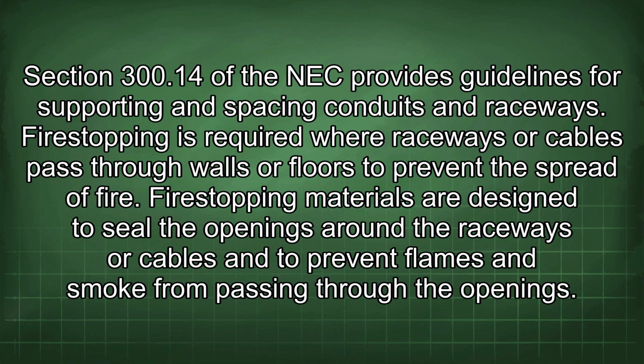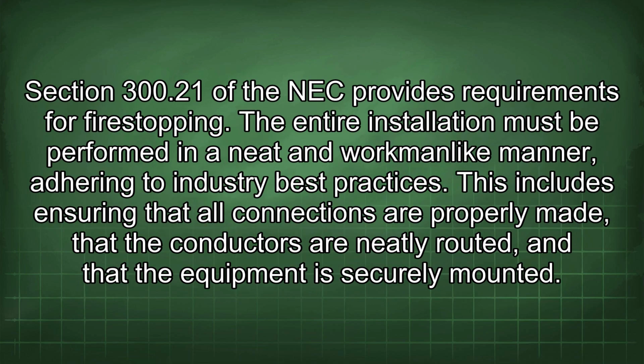Fire stopping is required where raceways or cables pass through walls or floors to prevent the spread of fire. Fire stopping materials are designed to seal the openings around the raceways or cables and to prevent flames and smoke from passing through the openings. Section 300.21 of the NEC provides requirements for fire stopping.